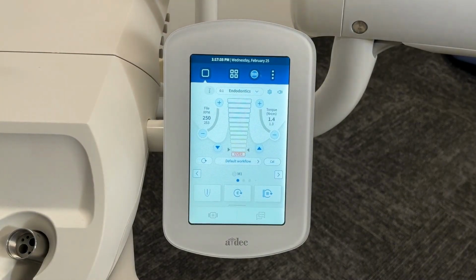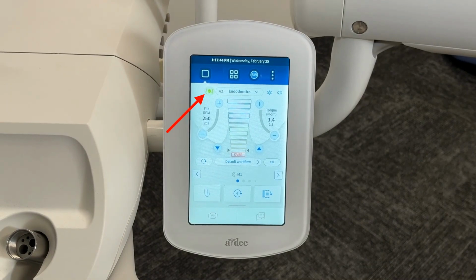Beginning at the top left of the screen, there is a handpiece icon. This icon shows whether or not a handpiece is ready for apex location. The icon is gray when continuity has not yet been checked between the file and the lip clip. Touching the handpiece file to the lip clip confirms continuity. The icon turns green to indicate apex location is ready for use with the handpiece.